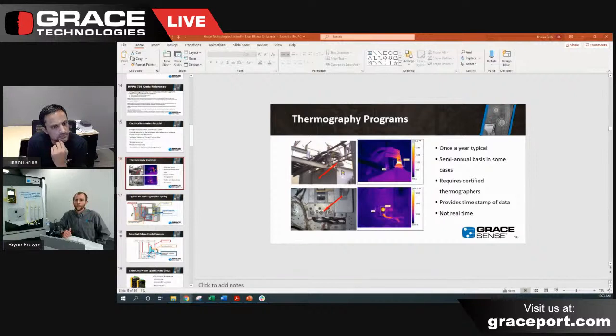And we don't know the condition of the loading. Was this at peak loading, or did we take a look when half the plant was down? Which is often the case, because they decide to do a thermography scan when it isn't as busy, or during a shutdown. We've had customers do it when most of their gear was down. So that's the big difference.